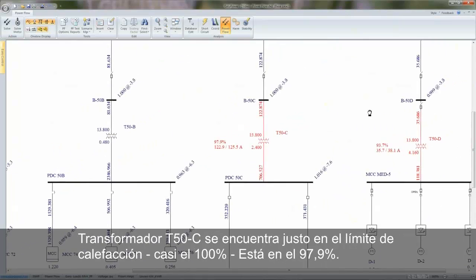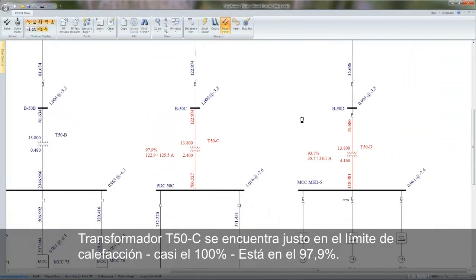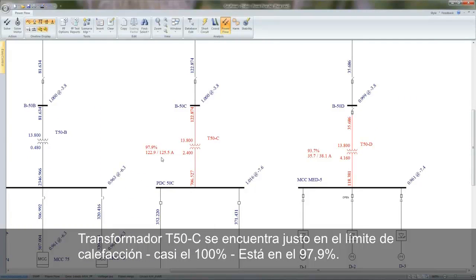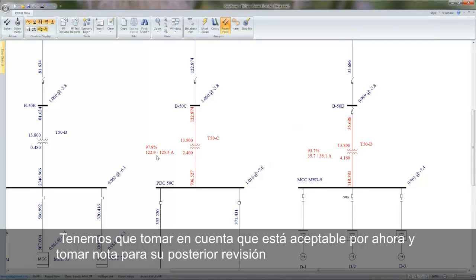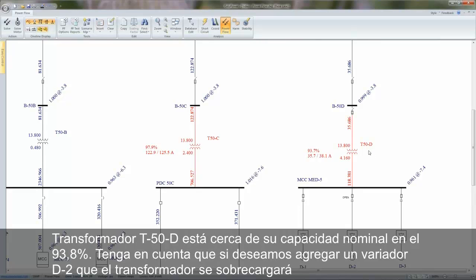Transformer T50-C is right at its heating limit of nearly almost 100%. It's at 97.9%. We'll consider that to be okay for now and make a note for later review. Transformer T50-D is near its rating at 93.8%.